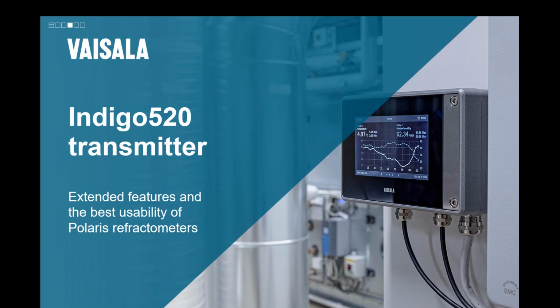Key to our sensors is keeping that prism clean. If it gets a coating that keeps it from seeing the process, there could be issues. A lot of ways to mitigate problems from a dirty sensor include increasing the velocity or using CIP. Using velocity keeps flow moving fast past the sensor. Mounting it in a 90-degree elbow creates a change in direction right at the sensor, which helps keep it clean before it gets dirty. We also have steam and water injection to keep it clean.